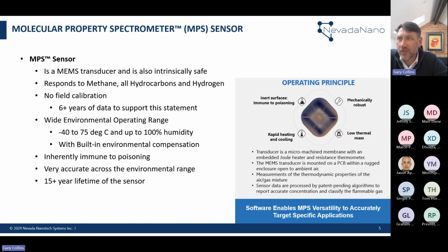The sensor itself takes advantage of the thermodynamic properties of air and gas. It has similarities to what you would class as a historical TC sensor, but this sensor responds really well to methane, all hydrocarbons, and hydrogen. It also does a fantastic job around refrigerants, but this webinar is focusing on hydrogen.